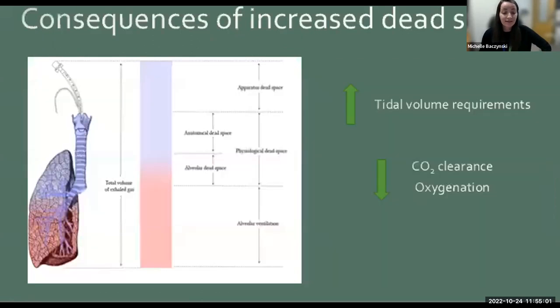In terms of the consequences of increased dead space on gas exchange, it is essentially the same effect as would be expected if you were to decrease ventilation. Both CO2 clearance and oxygenation would decrease. As dead space increases, the efficiency of ventilation is decreased, and as a compensatory mechanism, you may observe your patient having increased work of breathing. So it's important to consider fixed anatomical and mechanical dead space in your ventilation strategy.